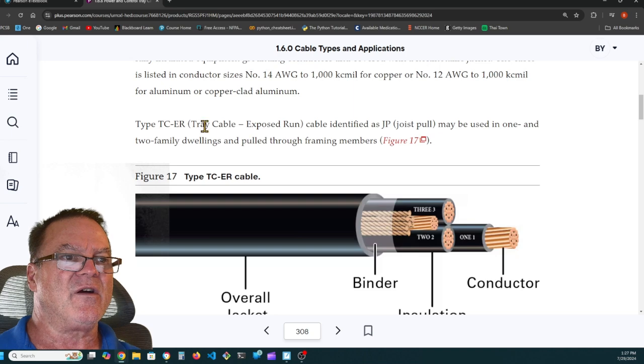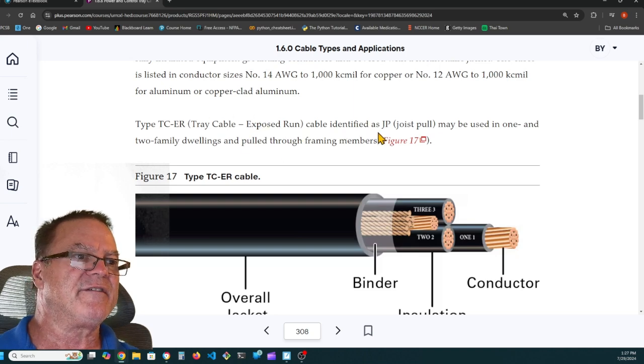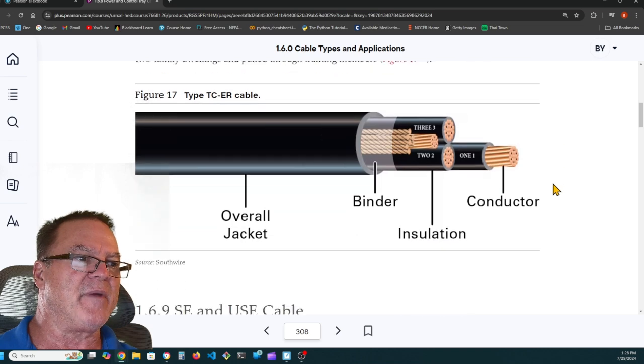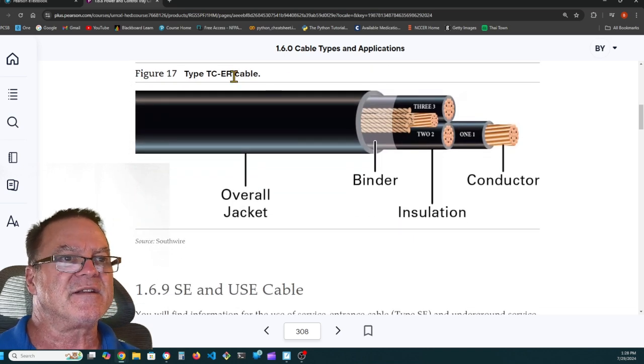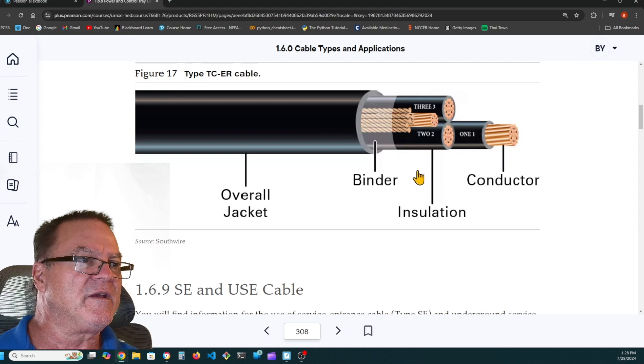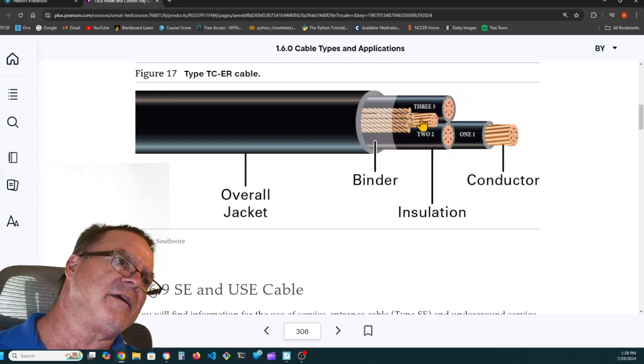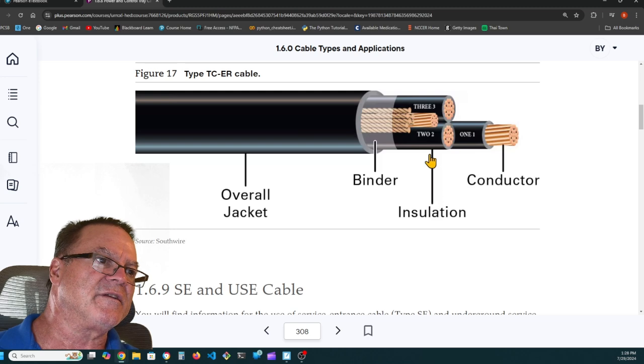Type TCER, tray cable exposed run cable identified as joist pull, may be used in 1 and 2 family dwellings and pulled through framing members. Is that TCER? So you've got 3 conductors. They're actually numbered 1, 2, and 3, and one of those can be a neutral. It looks to me like they've got a bare neutral and they've got grounds. They're saying that's called the binder, the overall jacket insulation.